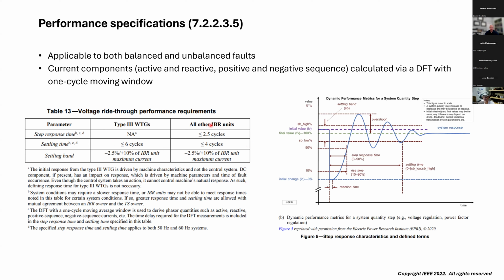We can take the final column here as an example. So the step response time needs to be less than or equal to 2.5 cycles, so here in North America, about 41 milliseconds. Settling time is less than or equal to 4 cycles. I've added the picture from some of the pre-phase material in the standard to give an idea that the step response time is the 0 to 90% time, and then the settling time is when you're in these two bands.